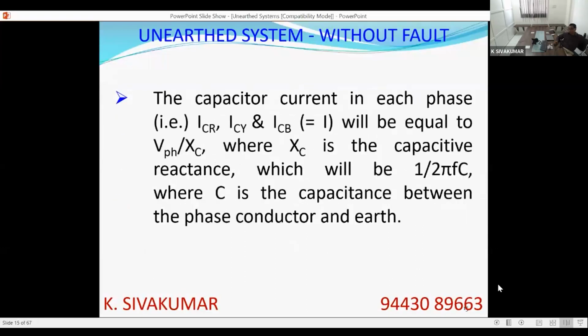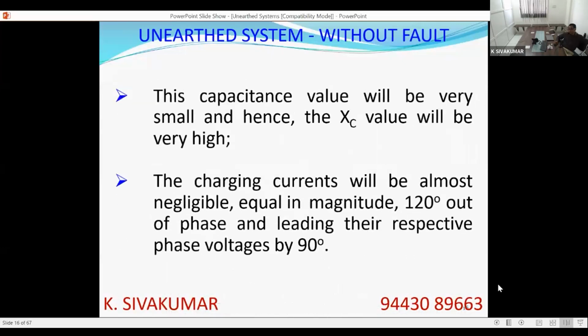The capacitor current in each phase, ICR, ICY, ICB, we assume will be I, equal to V phase by the capacitive reactance, which is 1 by 2πfC, where C is the capacitance between the phase conductor and earth. This capacitance value will be very small, and the XC value will be very large, because the dielectric distance is very high. Since the capacitance value is small, the capacitive reactance will be very high. Since the capacitive reactance is very high, currents are very small, negligible.